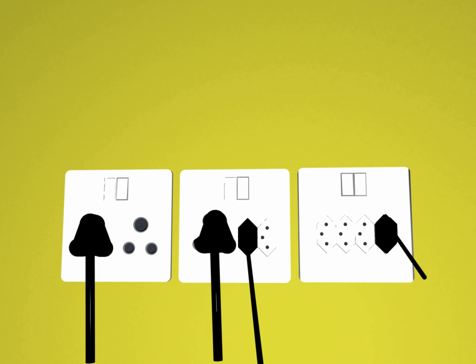Ambiguity between line and neutral on SHUKO. Since the SHUKO plug is non-polarized it can be inserted upside down, and therefore electronic equipment with SHUKO plugs must be fitted with double pole switches and fuse links on both the line and neutral pins in order to be safe. Requiring these extra safety features can add to the manufacturing costs of electronic equipment.